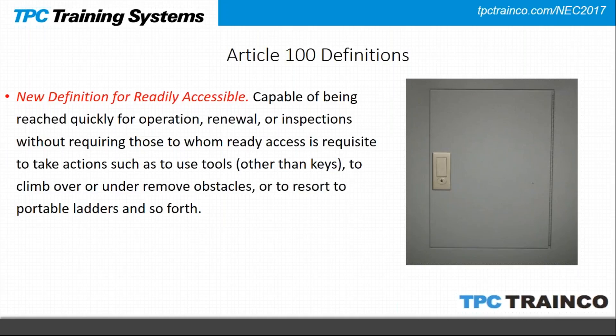The definition for readily accessible has always meant capable of being reached quickly — you don't have to move anything or get a ladder. A common question was: what if the panel is locked? The answer is it is still readily accessible, because it is under 24-hour supervision and qualified people possess the key. The Technical Committee has now clarified this by adding the phrase 'other than keys' — so if it is locked but supervision is present, it is still readily accessible.